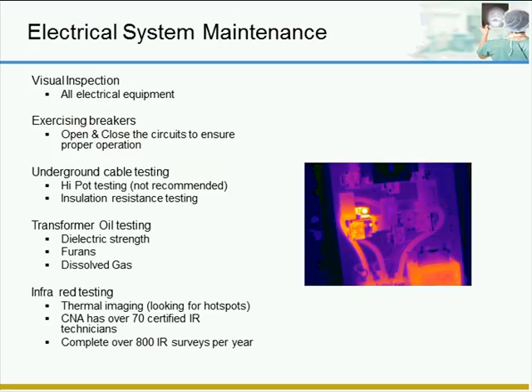The transformer oil testing on wet type transformers, do a test for dielectric strength, furans, dissolved gases. What this will tell you is the properties of the insulating fluid and the transformer insulation paper. You'll be able to see what gases are in the fluid. For example, acetylene. If you find acetylene in your transformer, that's a sign that you have internal arcing. That's bad. That means that your transformer is potentially about to fail.